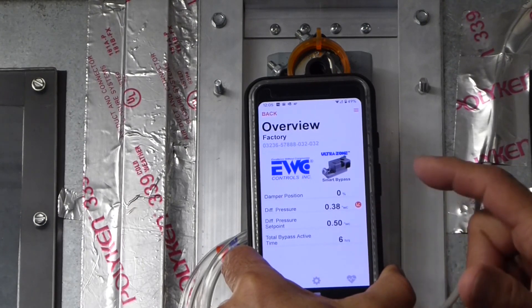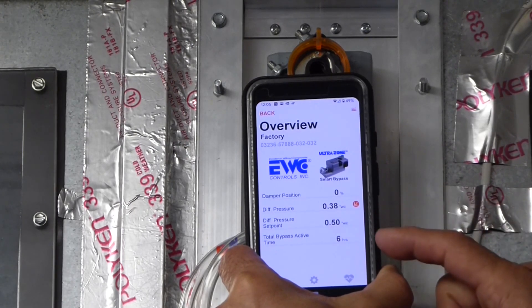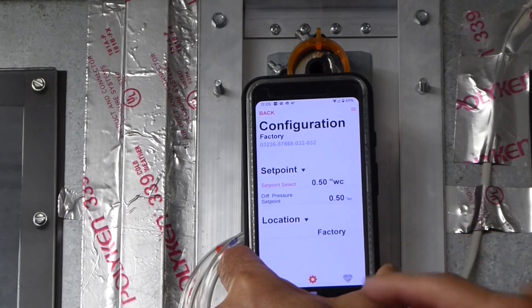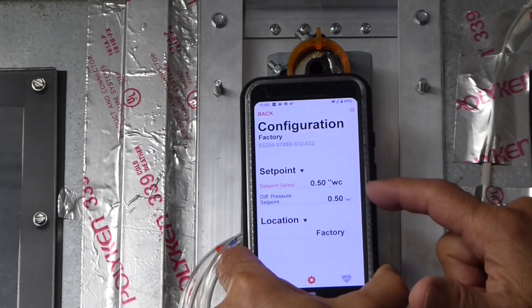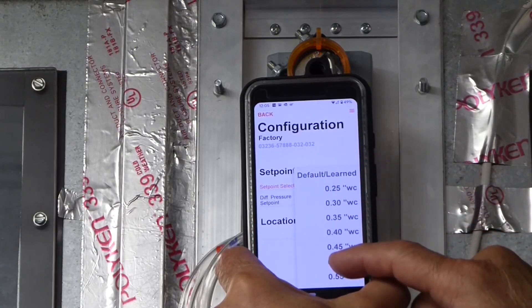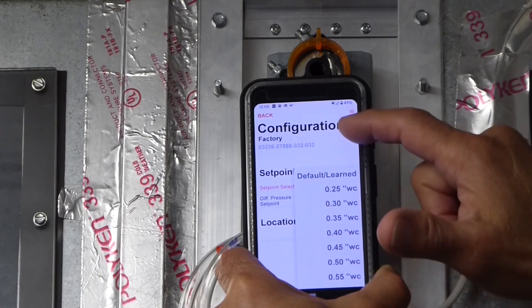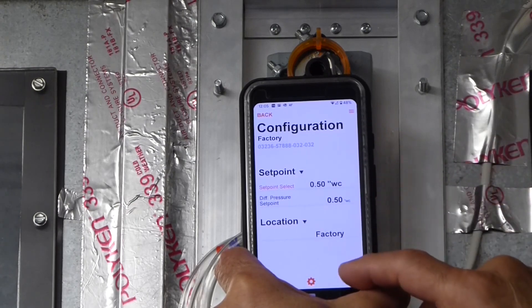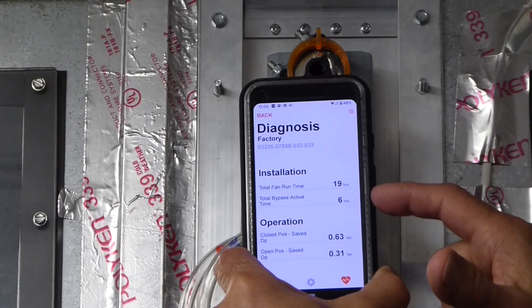See the total number of hours the smart bypass damper has been actively modulating since it was installed. See the non-zone static pressure that the SBD-2 learned and adopted as its own static pressure set point during the automatic setup routine. If desired, you can manually change the learned static pressure set point to a new static pressure set point of your choice. You can also see the total number of hours the indoor fan has been running since the SBD-2 was installed.